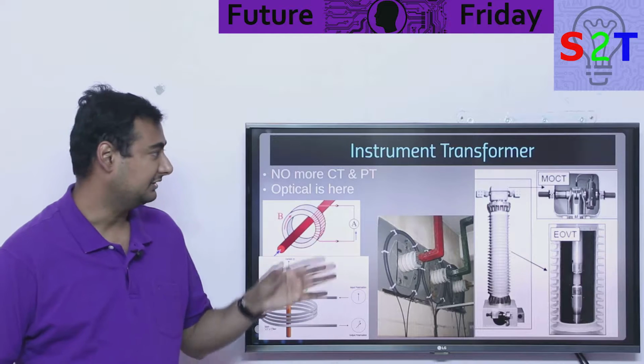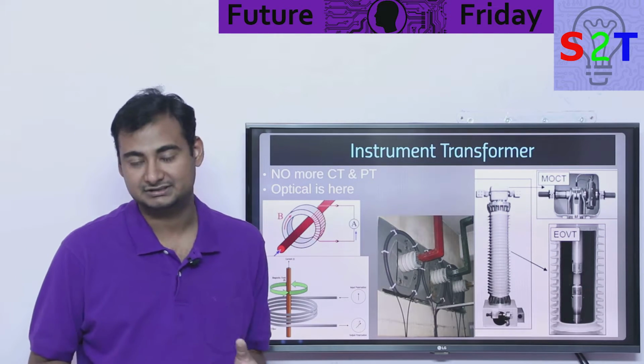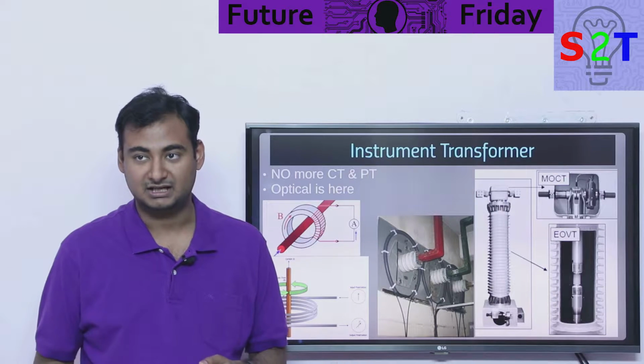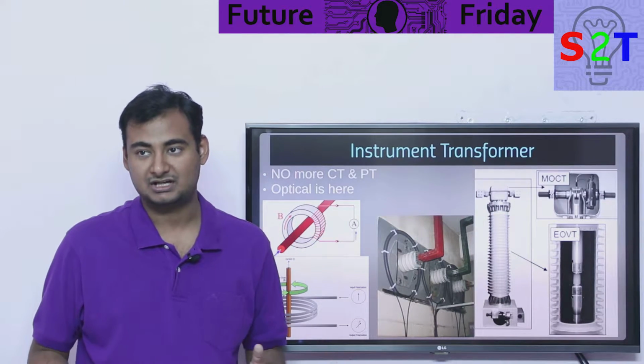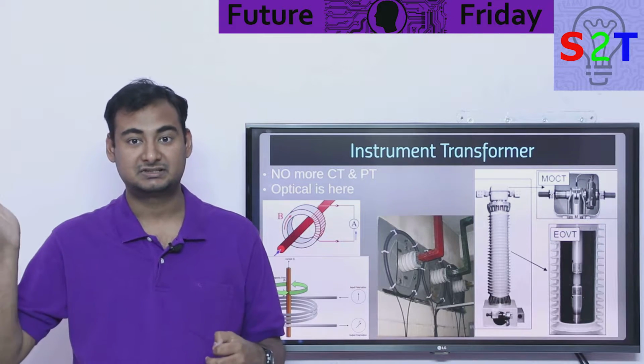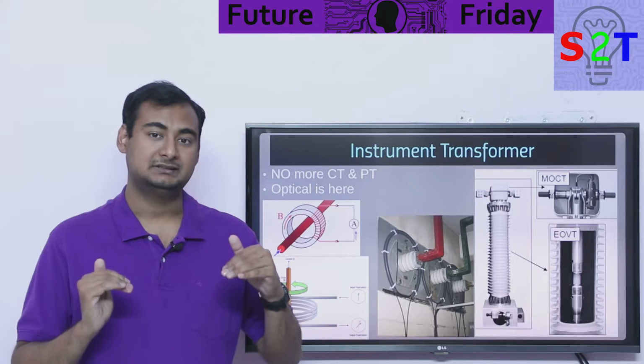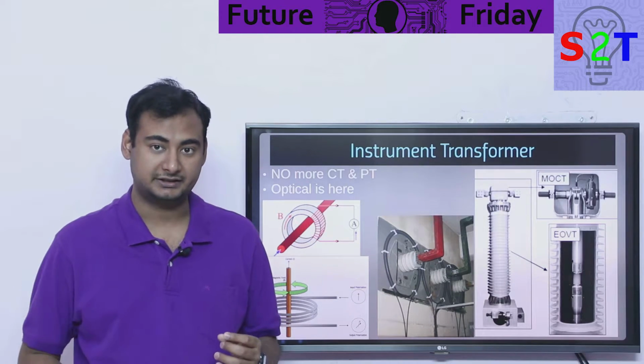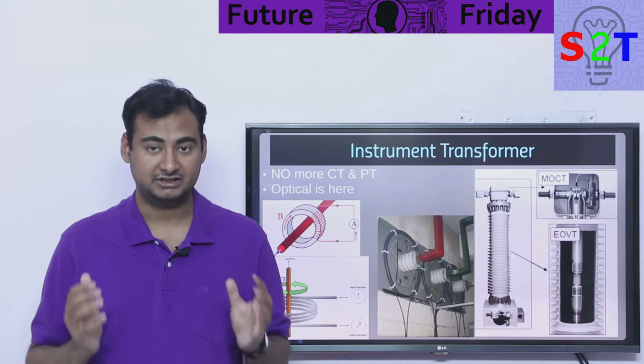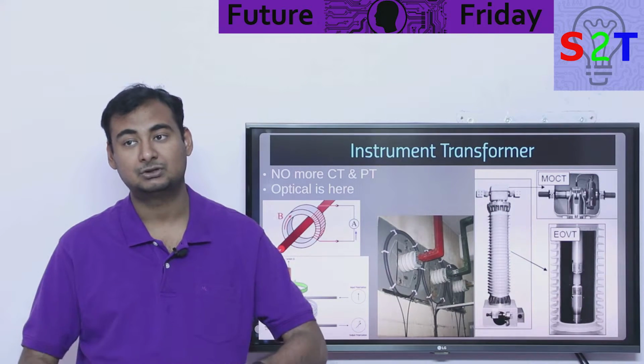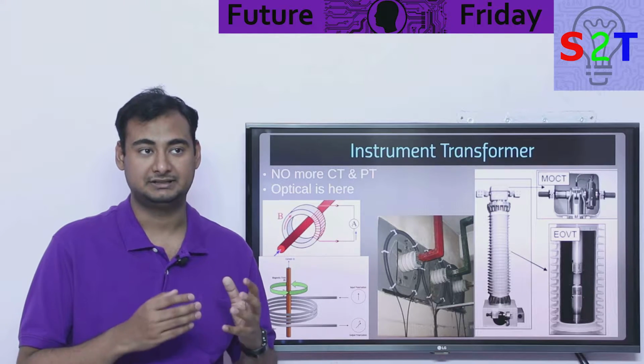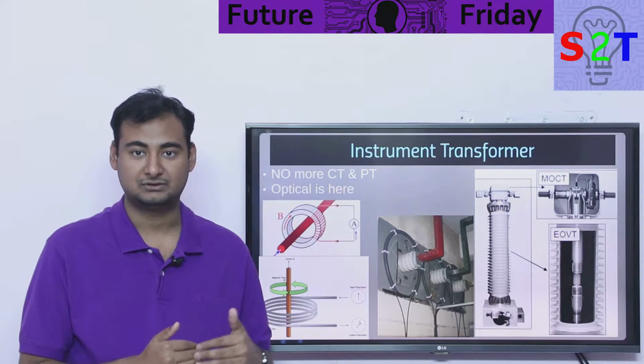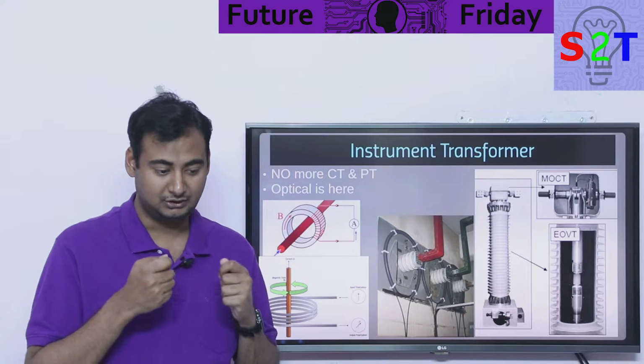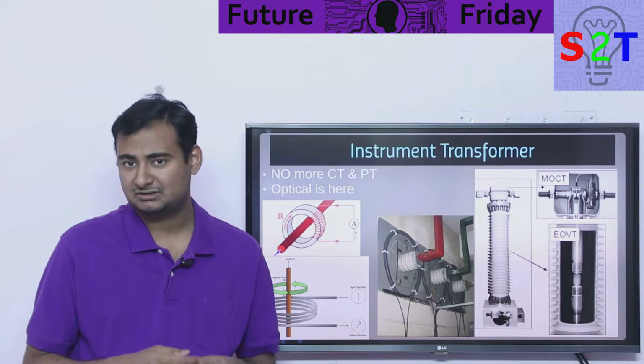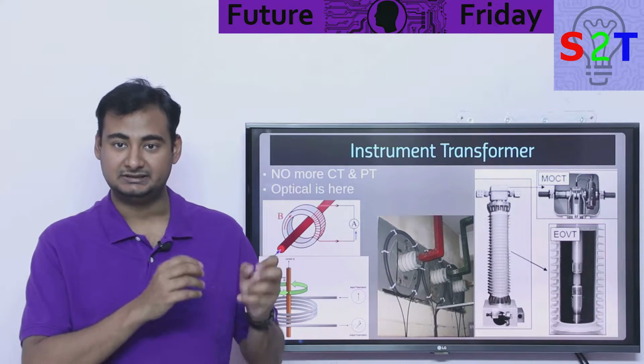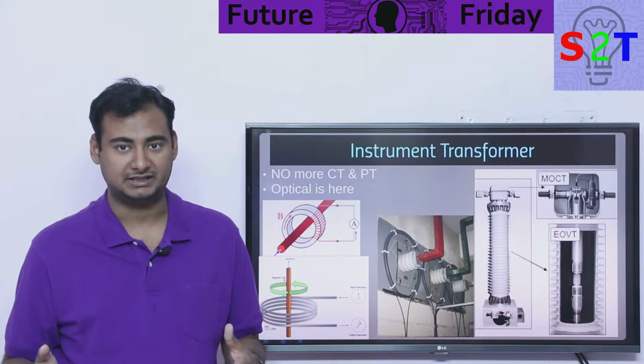So the first thing that's gonna go is our instrument transformers. If you're familiar with substations, and if you've checked my last video, we use basically two transformers. One transformer is just for measuring voltage, stepping it down so we can measure it accurately, and another current transformer which steps down the current so we can measure it accurately. These two things are very expensive, very big, very beefy, and they put a load on the structures themselves, leeching off around 1 to 2 amps of electricity just by running. You're measuring it, but also losing electricity. When you have thousands of substations, that leaching starts to pile up.